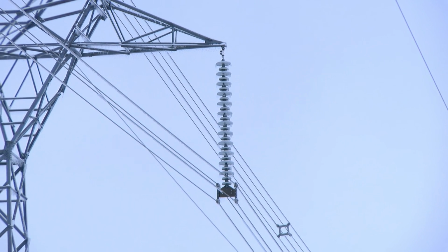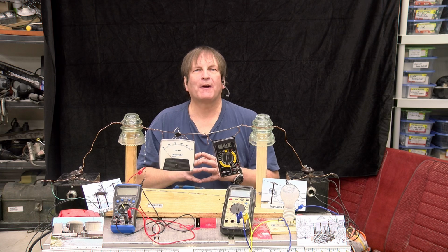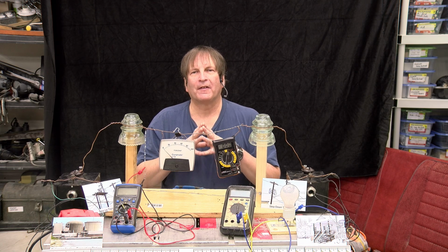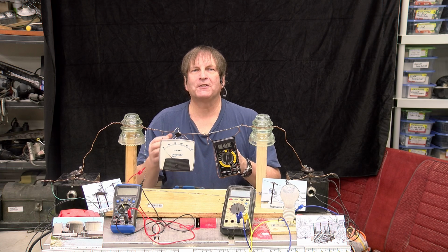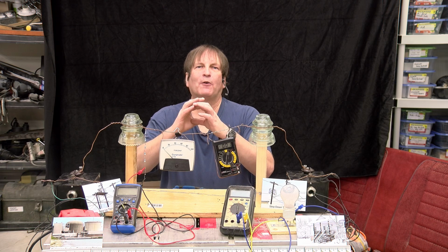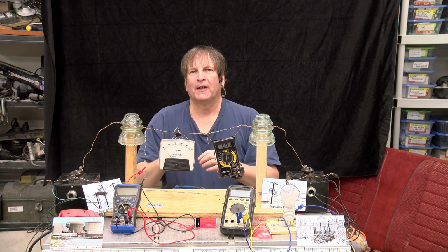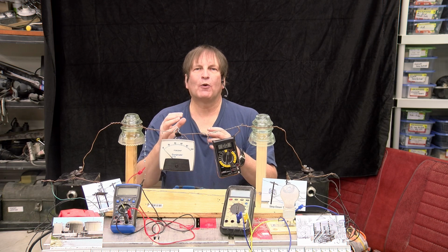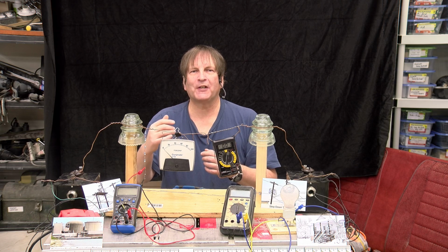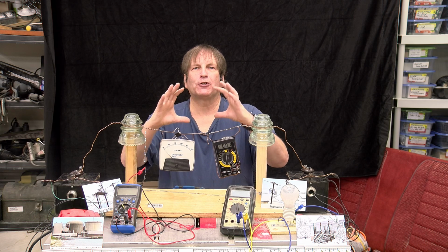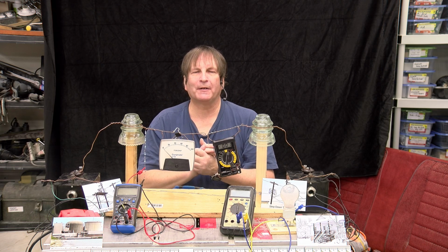And you might be wondering why they've done that. Well, there's probably 2 reasons. And they all have to do with creating an effective diameter of the power transmission wire. If you have a very narrow wire, the electric field at the edge of the wire is much higher than if you have that same voltage on a much larger diameter wire.